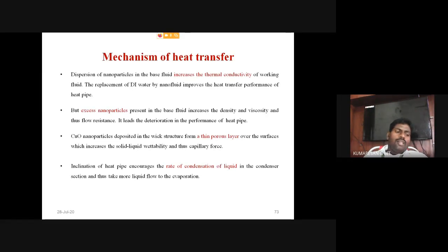That's why the heat pipe filled with the 1.5 weight percentage deteriorates the performance of the heat pipe. Then copper oxide nanoparticles or aluminum oxide nanoparticles deposited over the wick structure form a thin porous layer over the surface, which increases the solid-liquid wettability, and also increases the capillary action. Then the inclination angle of the heat pipe increases the rate of condensation of liquid in the condenser section.